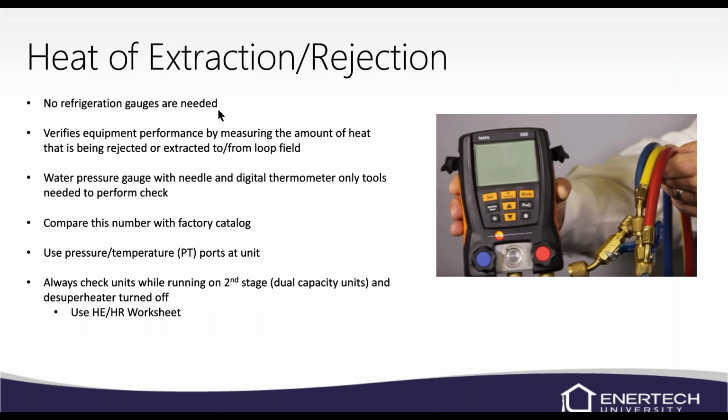Again, no refrigerant gauges needed in heat of extraction, heat of rejection. You can leave those on your truck until you realize you need them. With a closed sealed system, every time you put refrigerant gauges on there, you're gonna take a little bit of refrigerant out. So we wanna make sure that we don't put the refrigerant gauges on if we don't need to.